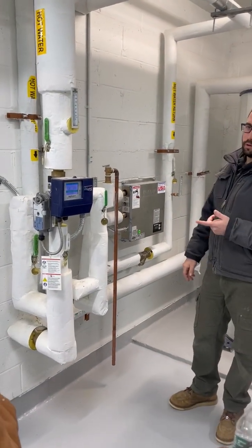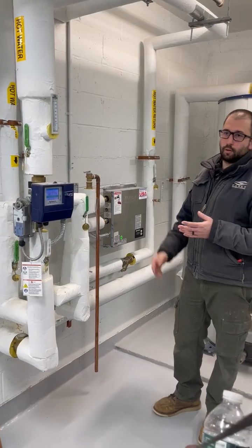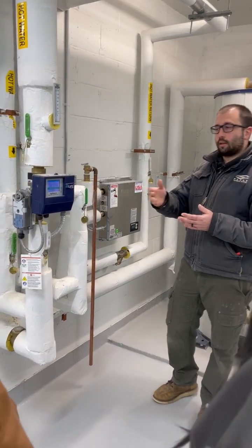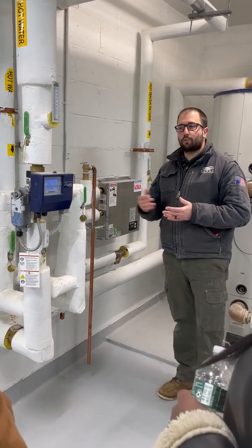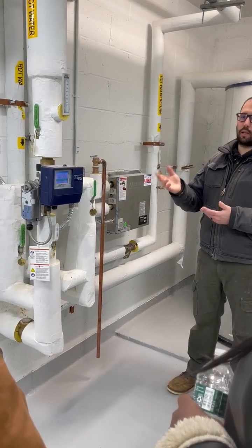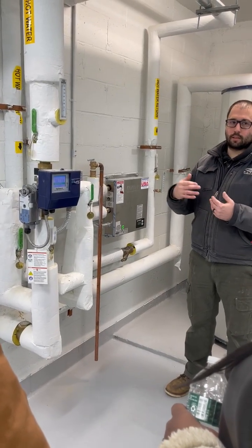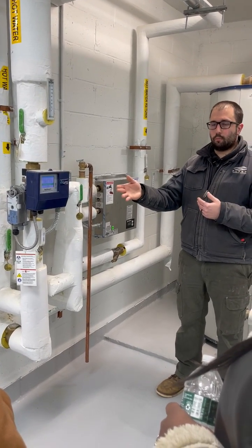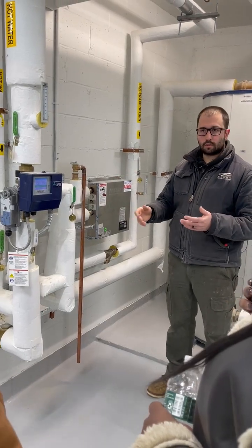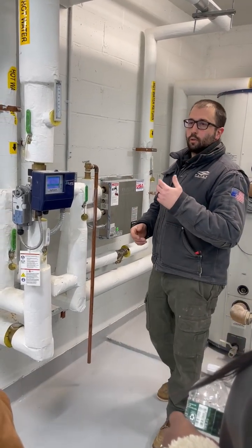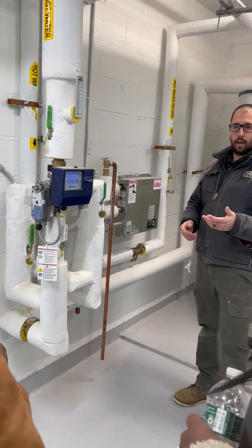The high temperature alarm for this is 135 degrees, so 15 degrees over. I can definitely change it if the building wants, but usually our standard is 15 degrees over. It's going to kick in for the high temperature alarm, that's if BMS wants to catch it, if you have a building monitoring system or anything like that. So it goes to building engineers, so they can look at it.